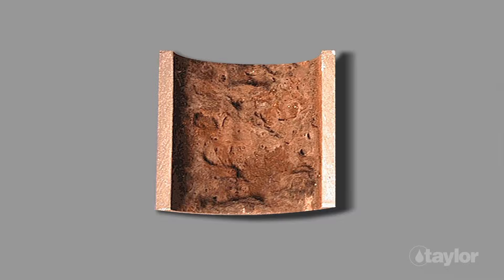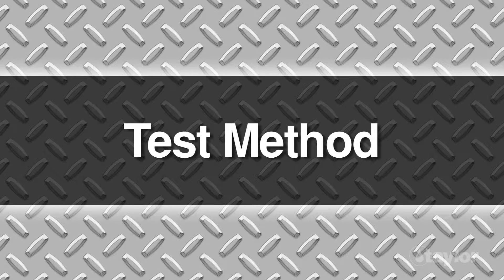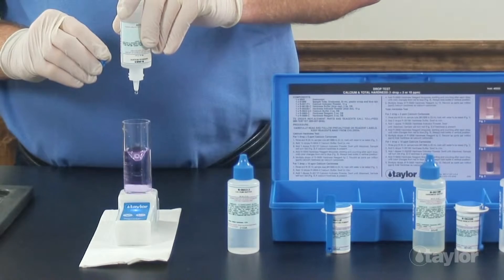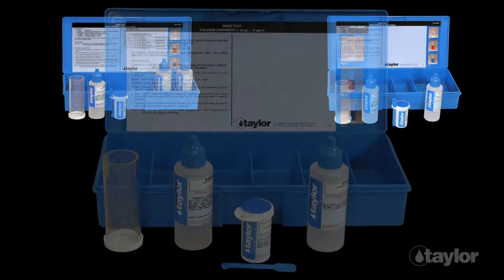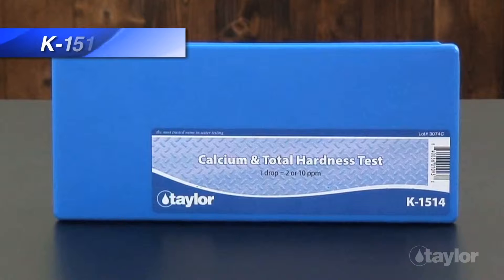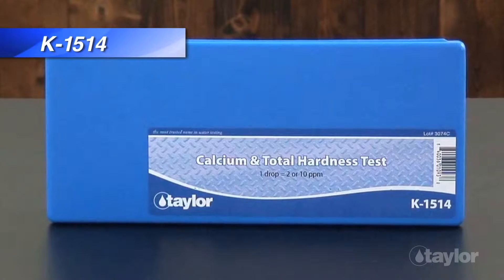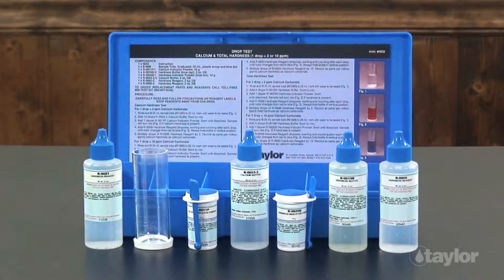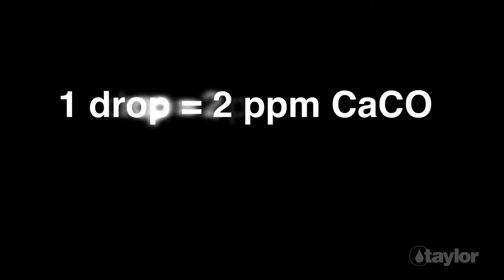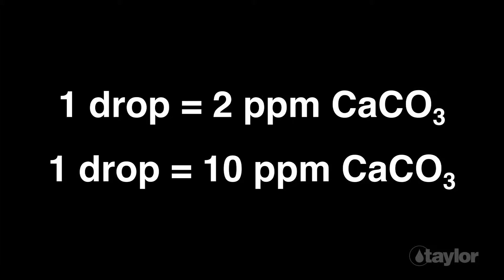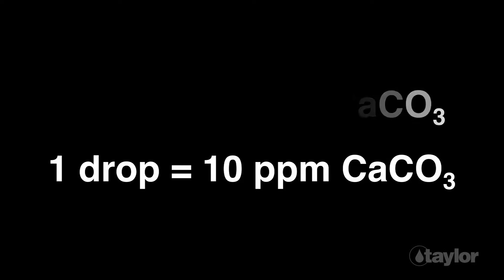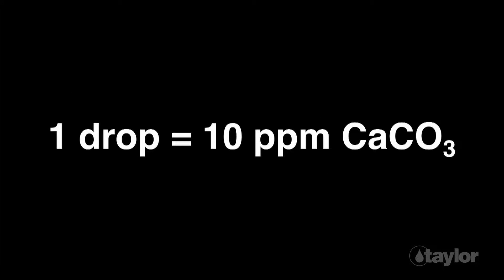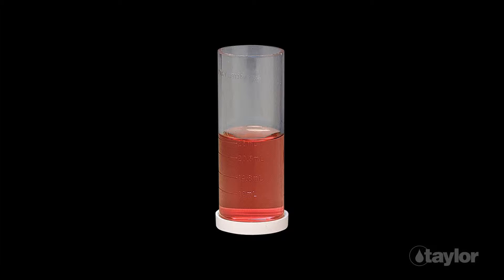For these reasons, calcium and total hardness are often tested in water to assure system reliability and water treatment program performance. It is critical to test water hardness on a regular basis, and Taylor offers several kits to help you monitor this parameter. For this demonstration, we will be using K1514, a simple drop test for determining calcium and total hardness. The K1514 allows for two equivalencies: one drop equals two parts per million and one drop equals 10 parts per million hardness as calcium carbonate. We will be demonstrating the one drop equals 10 parts per million method in this video.